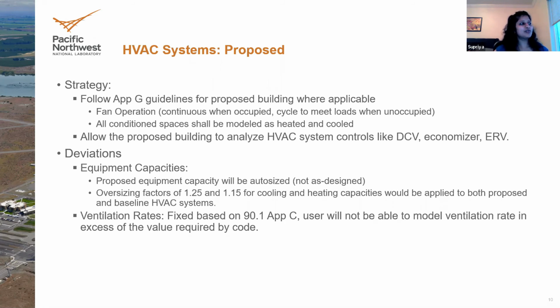Ventilation rates: Appendix G says this should be as-designed, but this would also be prescribed based on values in Appendix C by building area type, and the user won't be able to modify this. The only exception is when a system has DCV control, in which case it gets adjusted for occupant density or CO2 sensors, whichever way we want to allow.